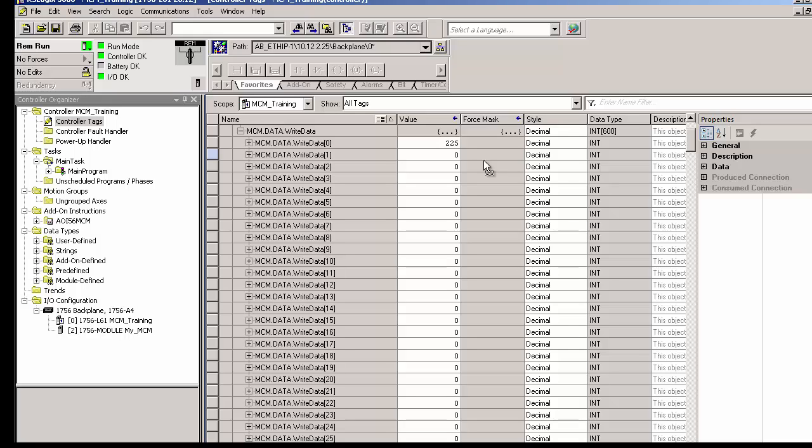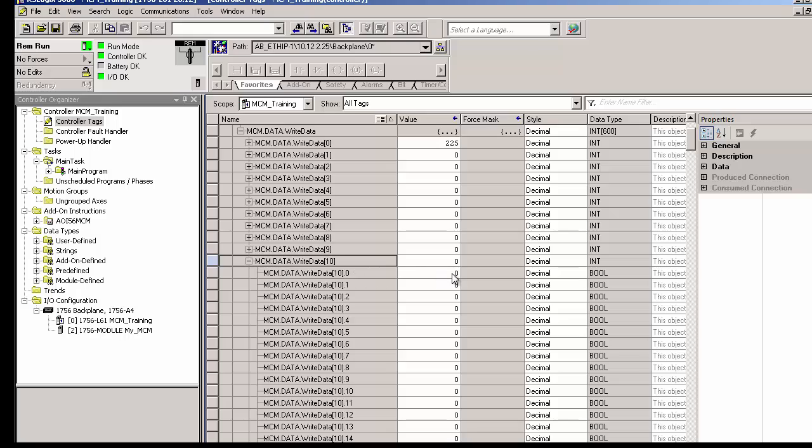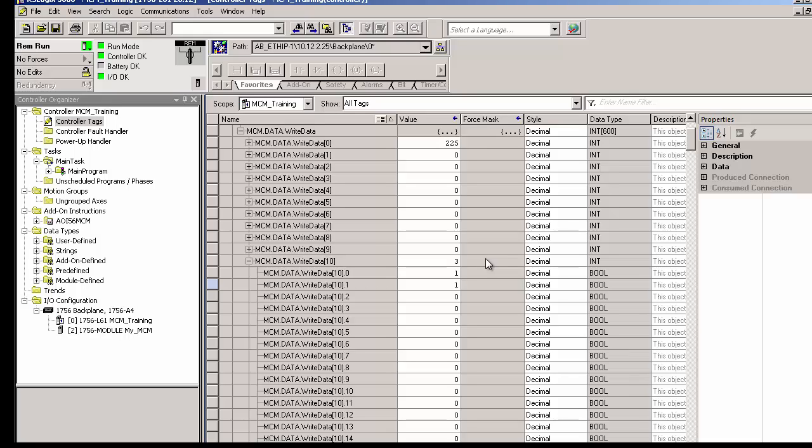In the second command, we wanted to set some bits in the power monitor to reset the minimum and maximum values for phase A. I specified the first bit would come from bit address 160 in the MCM's write data array. This means that we'll go to word 10, this will be MCM.data.writeData 10, and we'll expand this out and set the first two bits here to 1. And these will be bits 160 and 161 in the bit level addressing.